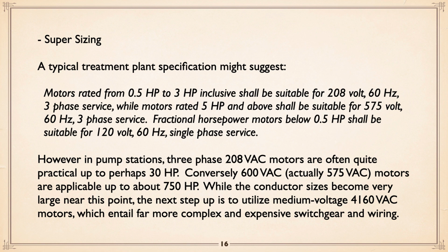Supersizing. A typical treatment plant specification might read: motors rated from a half to 3 horse shall be suitable for 208 or 600 volt 3-phase service, while motors rated 5 horse and above shall be suitable for 575 volt. Fractional horsepower motors below a half horse shall be suitable for 120 volt, 60 hertz single phase.